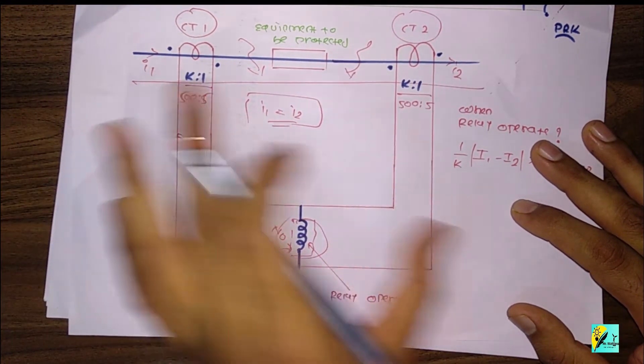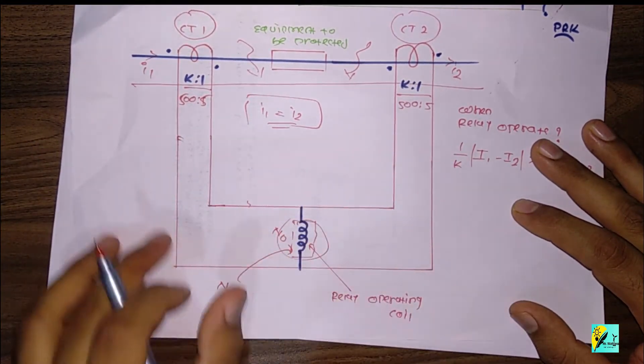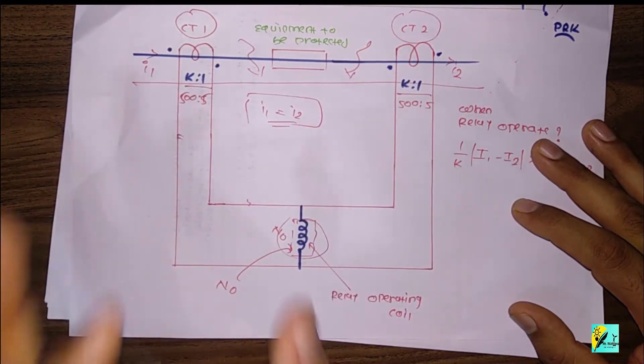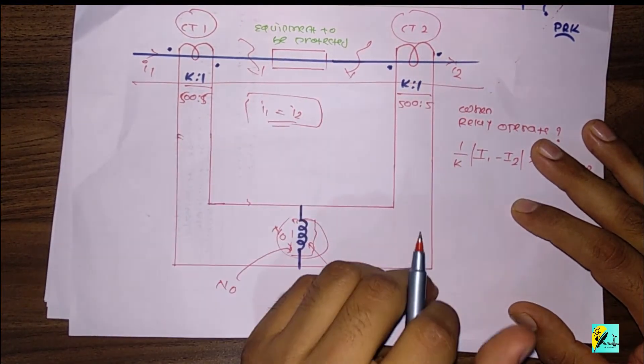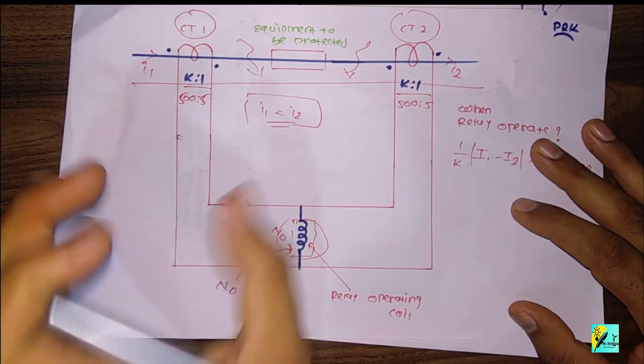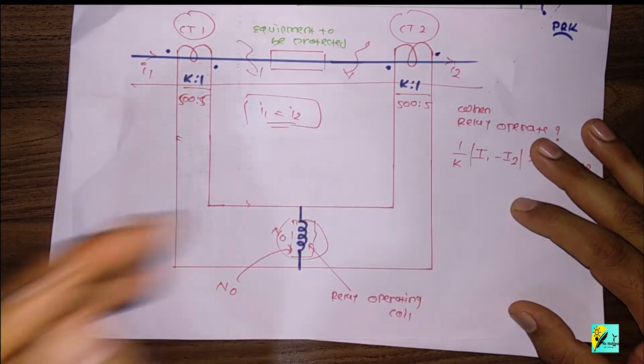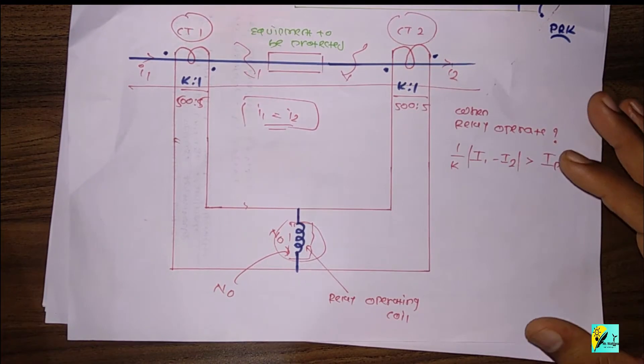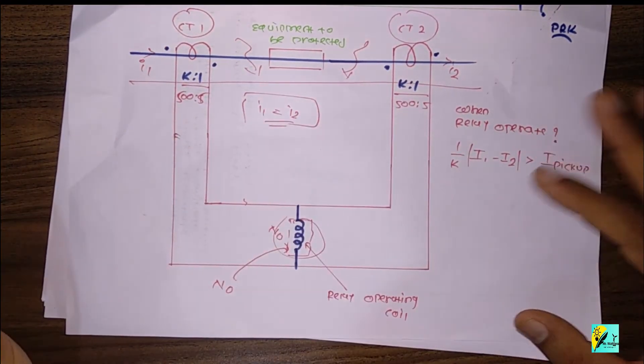If there is no fault, I1 should equal I2, but their secondary currents will only be equal if the transformation ratios are equal. They may or may not be equal due to two factors. The first factor is saturation — transformer cores can saturate, causing the turns ratio to become unequal. The second factor is if the CTs are not identical in nature, the transformation ratio will not be equal.